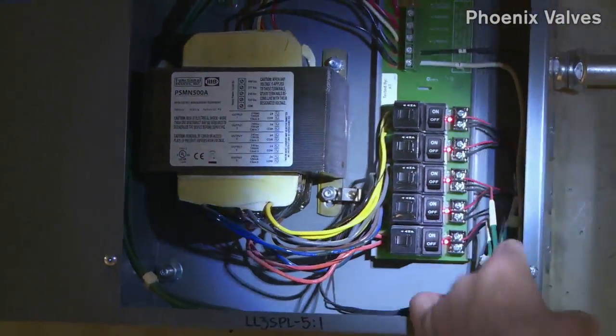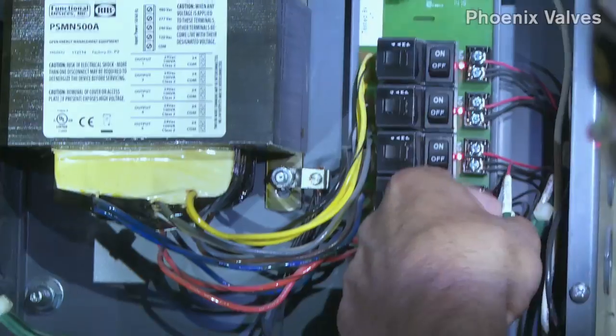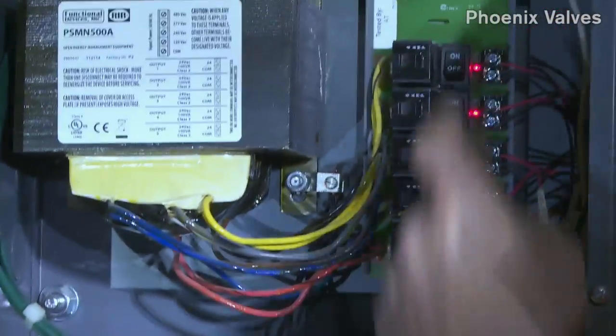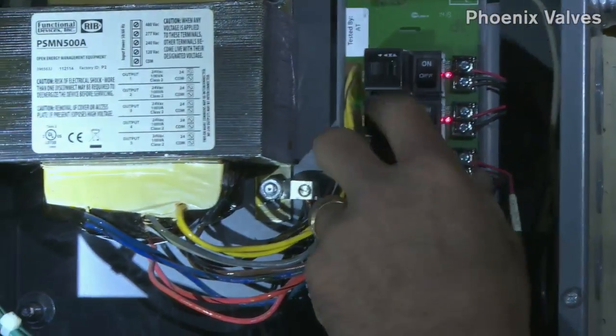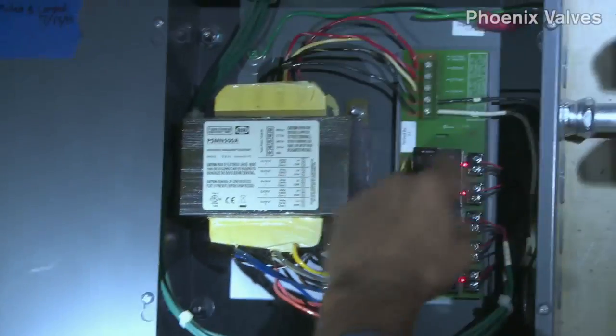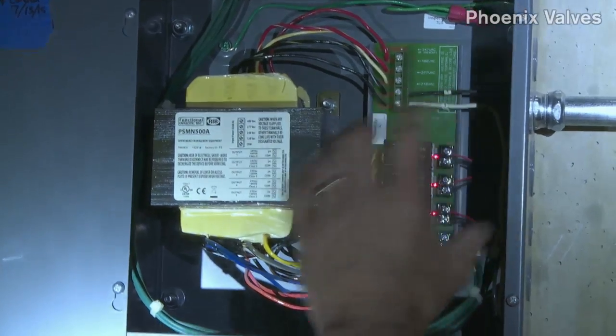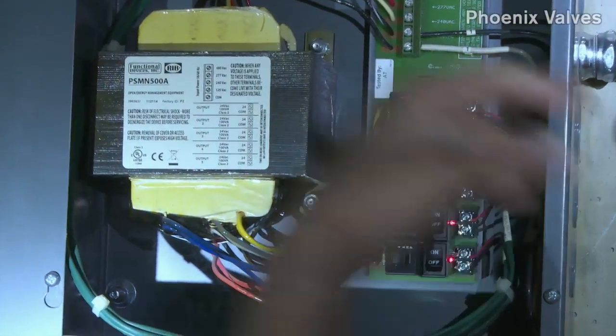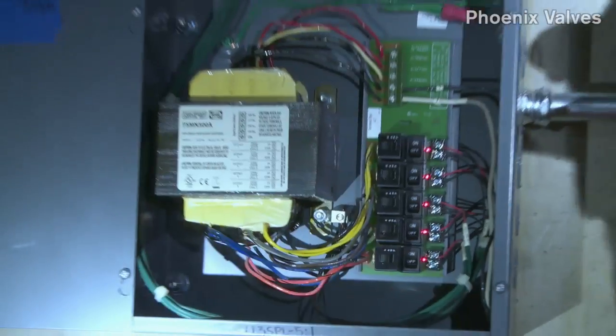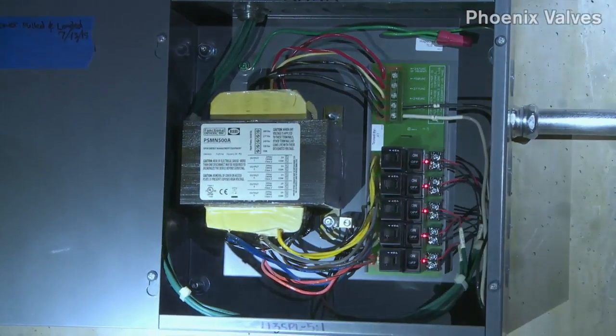You have all these wires, and I believe they're all labeled to what they go to. If any of these is off, they all have their own individual circuit. This is a 500 VA total transformer with 5 individual 100 VA circuits. Sometimes if something happens and a wire gets nicked and it gets shorted out, it'll trip at this circuit right here.